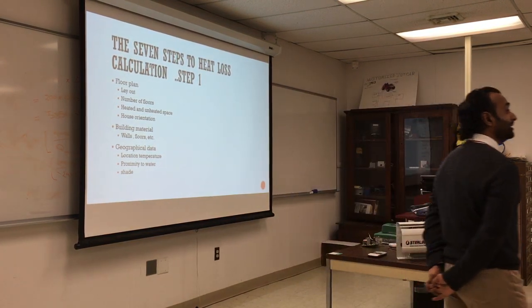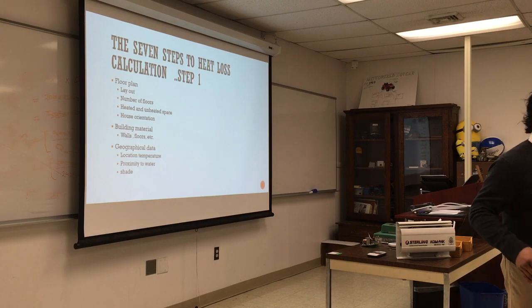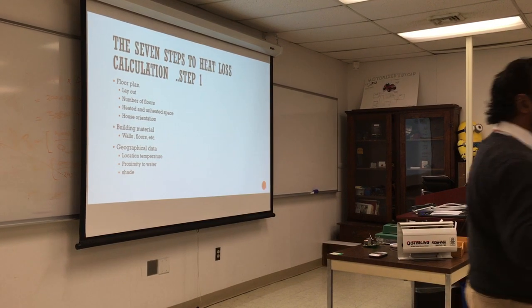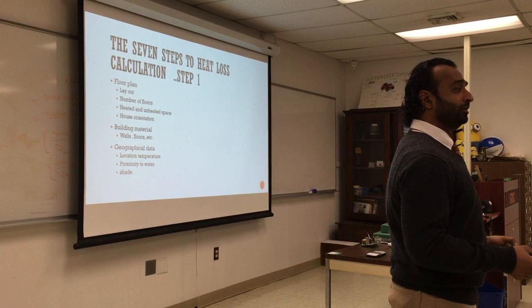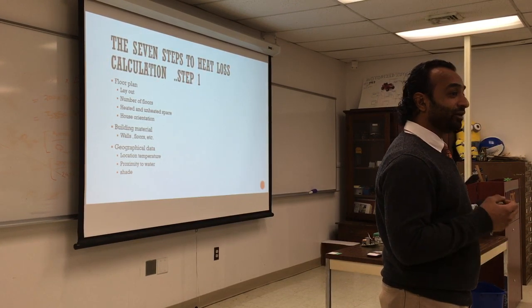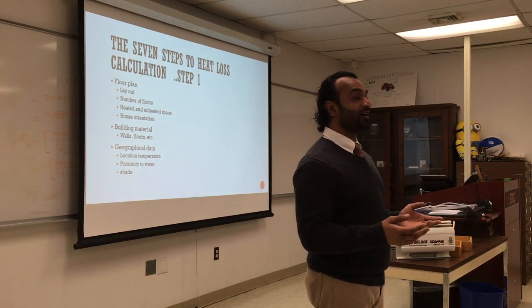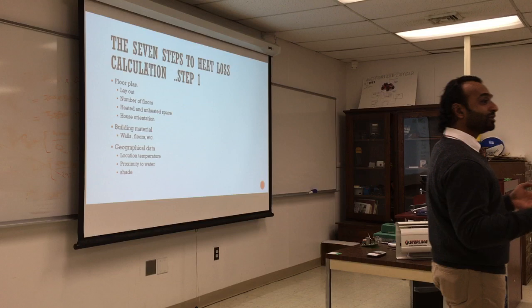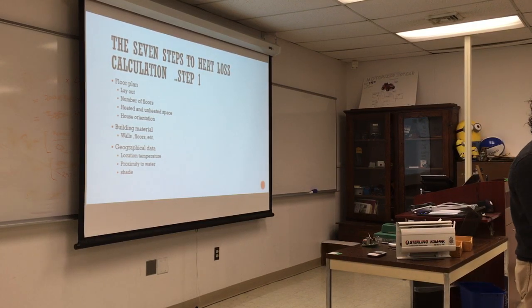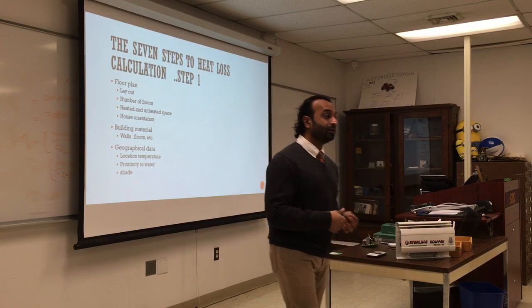That's a lot. Besides the money, even if you're filthy rich, that's a lot of carbon dioxide and combustion going on. Ideally, you want the house to have the least amount of BTUs, and the only BTUs you will lose is through air exchange. If you have a really airtight house and the insulation is perfect, probably you're gonna lose 5,000 to 10,000 from the entire house, and some from the air exchange to the outside, because you need that to breathe. Which is possible, by the way, if you really make it.